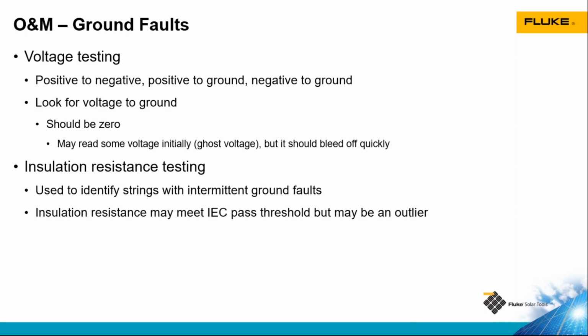That's just called ghost voltage. We can also use insulation resistance testing to find circuits that have a ground fault. If we're testing our strings of modules, we can use that type of test to find which string has the fault. It's not going to tell us where the fault is, but it's going to give us an idea of which circuit has the problem.